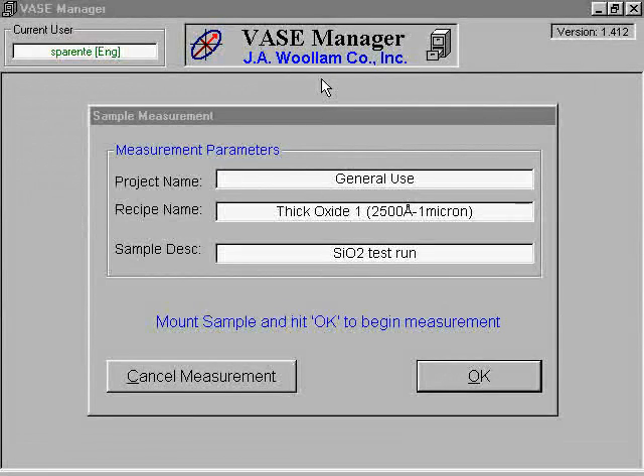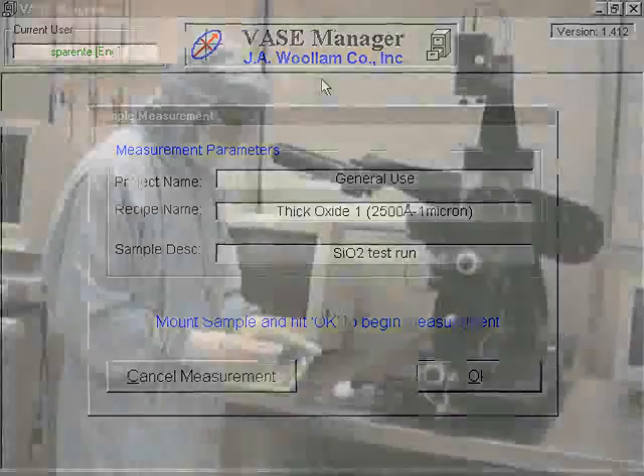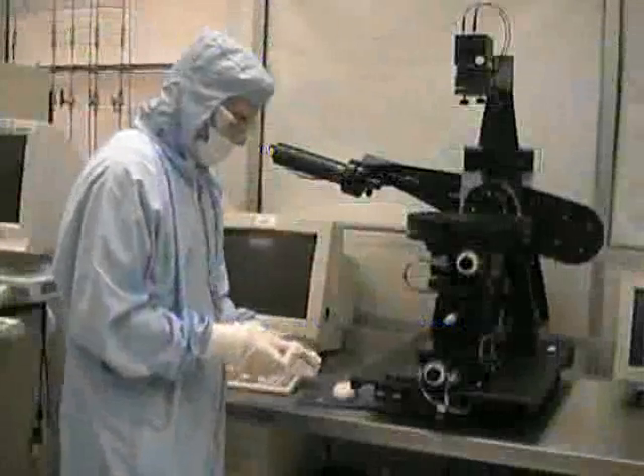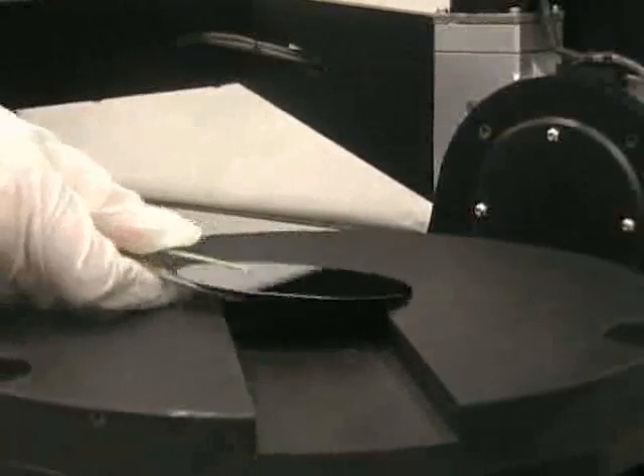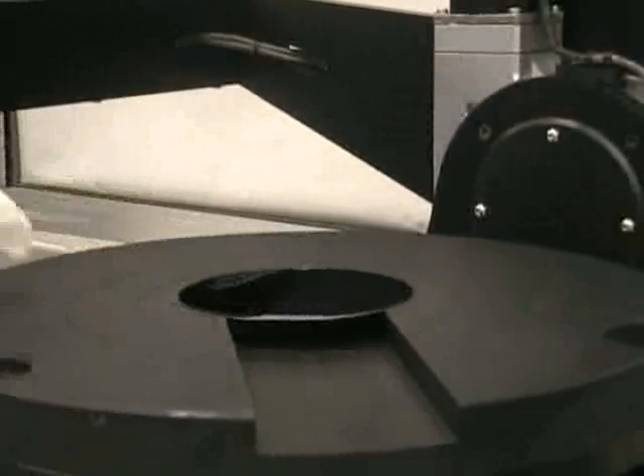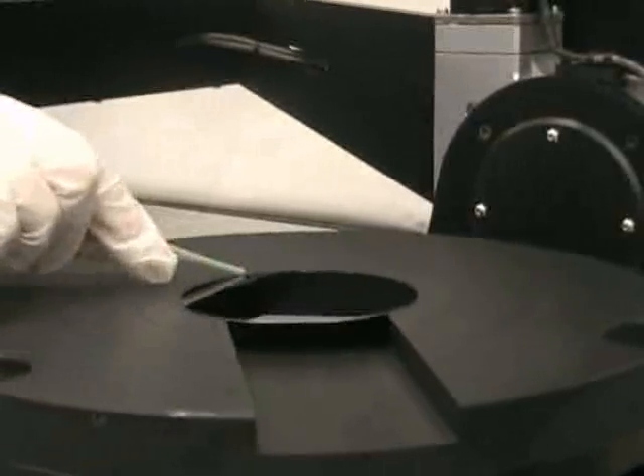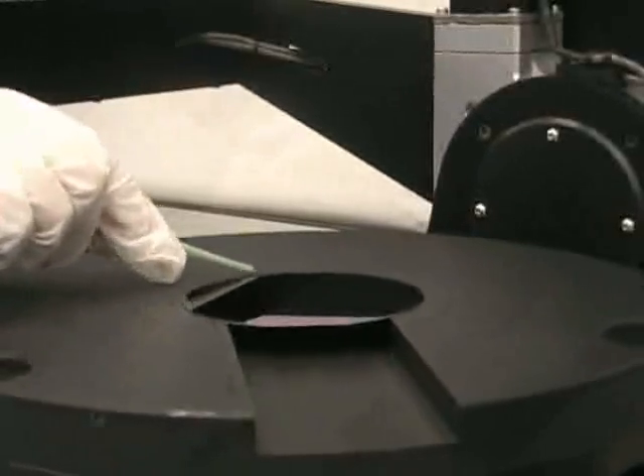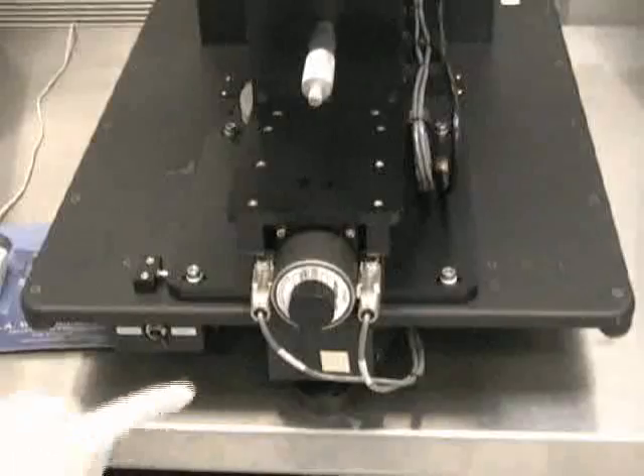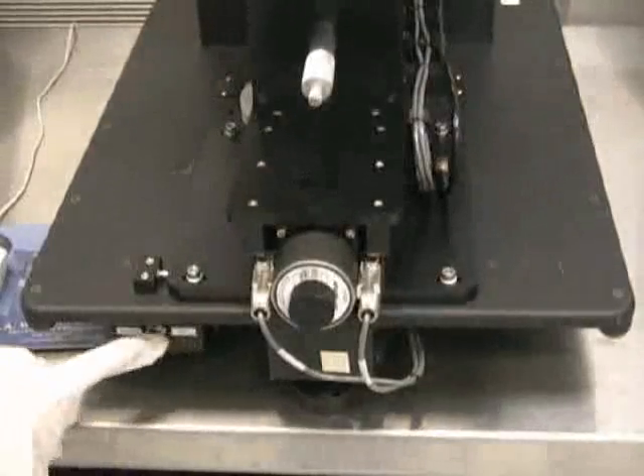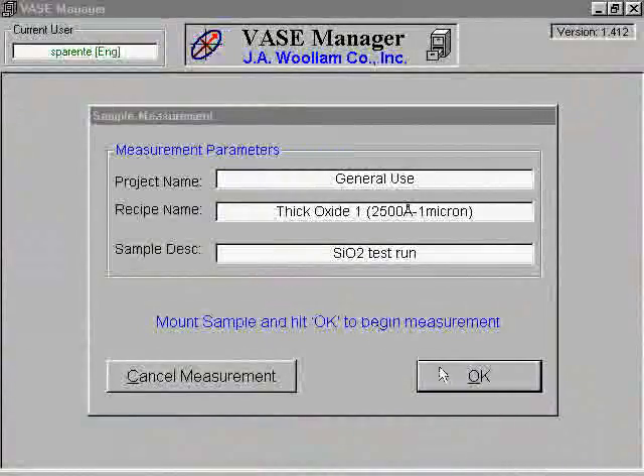You will now need to prepare the ellipsometer for the scan. The software will provide you with a summary of the scan that you have set up. If this information is correct, place the sample onto the sample stage. It should be roughly centered, but does not need to be exact. Flip the vacuum switch, which is located at the base of the ellipsometer, to Vacuum, and then select OK.